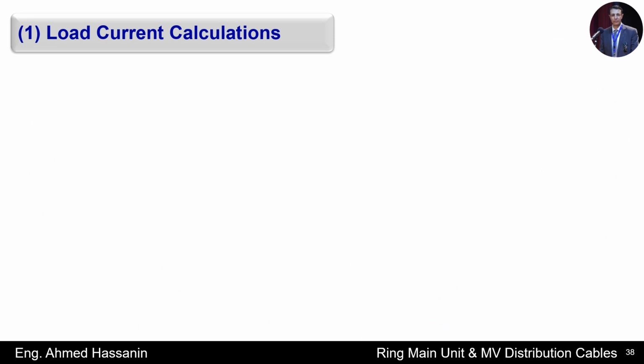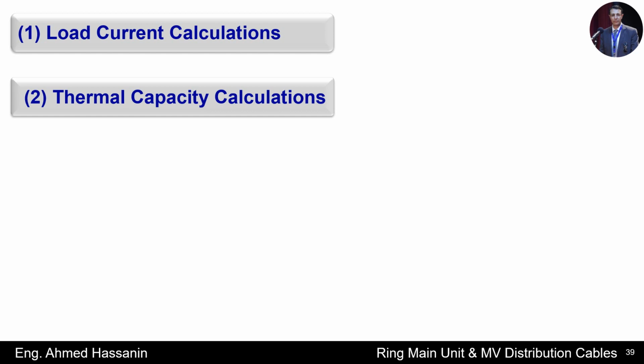Through the previous data of the ring system, in detail and step by step, I will explain how to calculate the total load current of this ring system. Also, I will explain how to calculate the load current that will flow through each part, or each medium voltage cable, of the ring system. Also, in detail and step by step, I will explain how to calculate the total thermal current of this ring system and the thermal current of each medium voltage cable of the ring system. In addition, we will know the technical difference between load current and thermal current calculations.